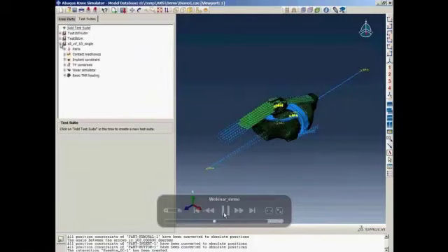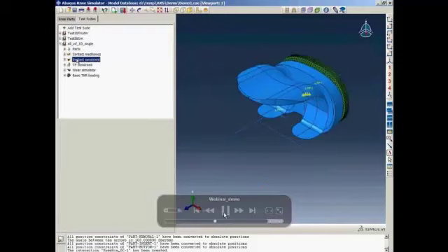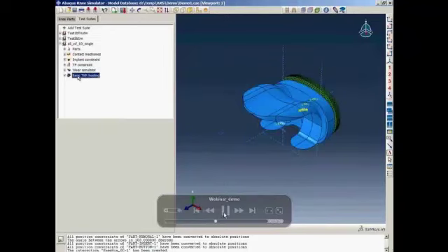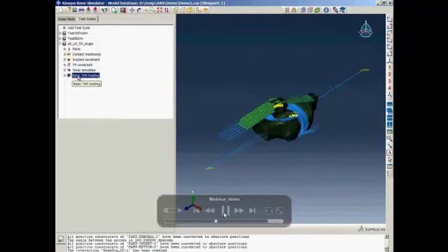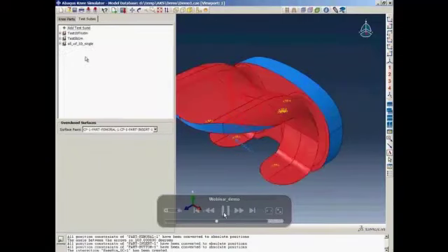Now we have the workflows generated. The user can go ahead and review each workflow: tibial-femoral constraint, wear simulator, total knee replacement. All the workflow models have been generated. Next, by right-clicking on the workflow, the user can access the interference check. Because there is interference between the two components I imported, they are highlighted.